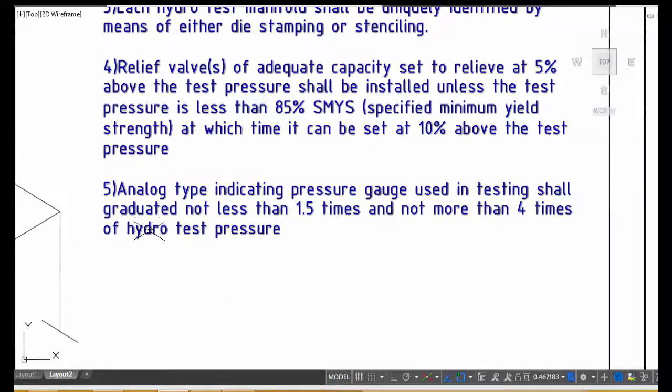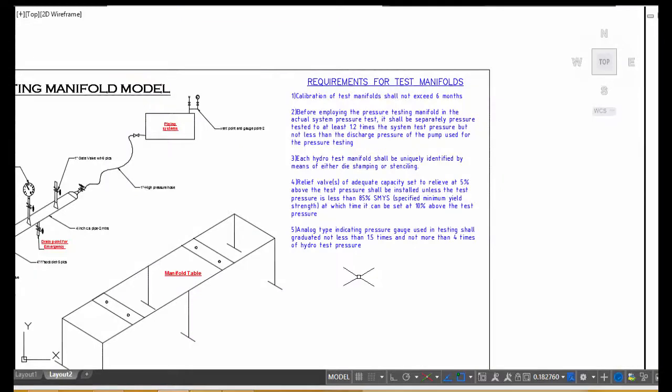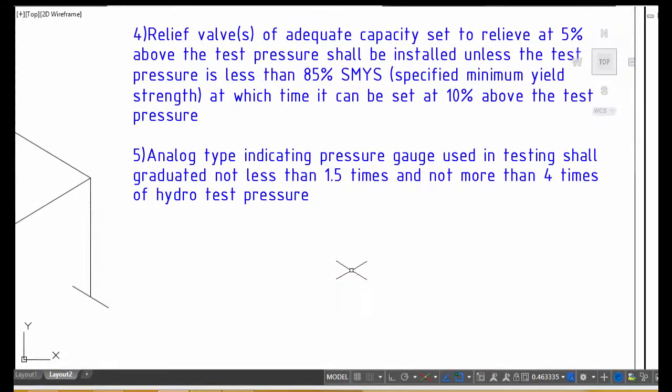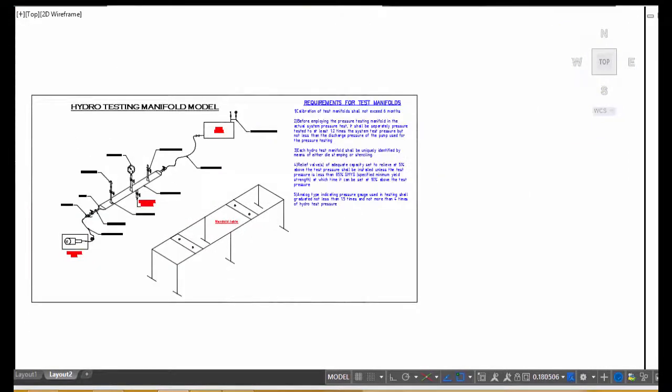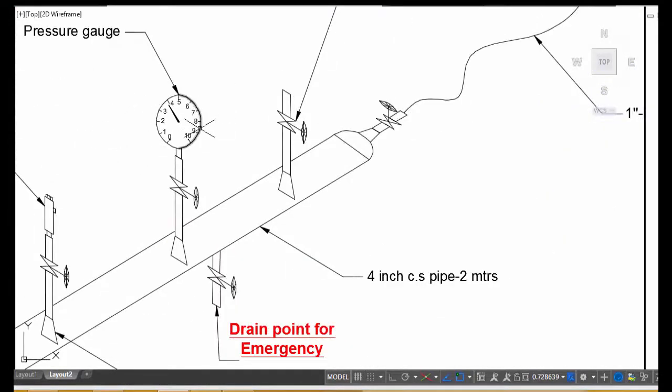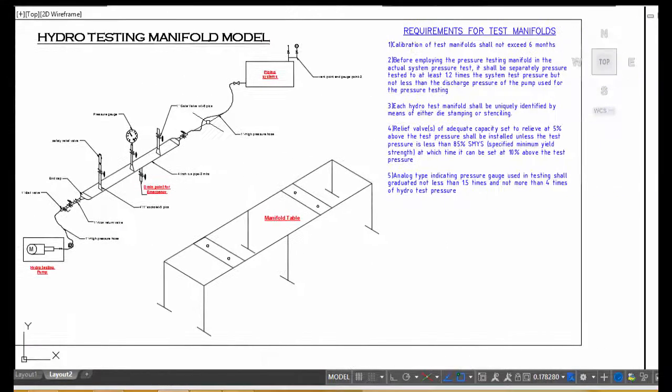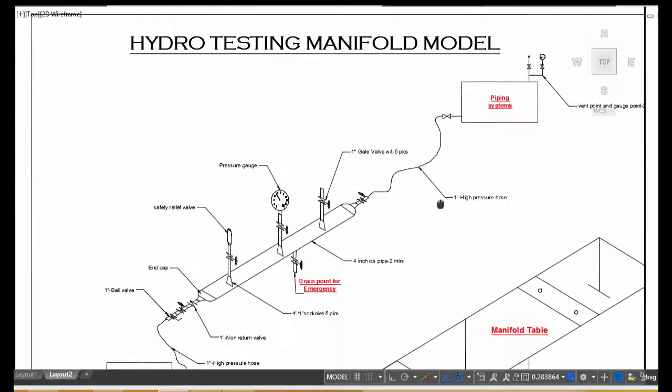And pressure gauge - it is allowed 1.5 times minimum and not more than 4 times of hydrotest pressure for accuracy purposes. For example, 4 bar means 4 into 1.5 times, so that range pressure gauge only you can use. Maximum 4 times you can use.